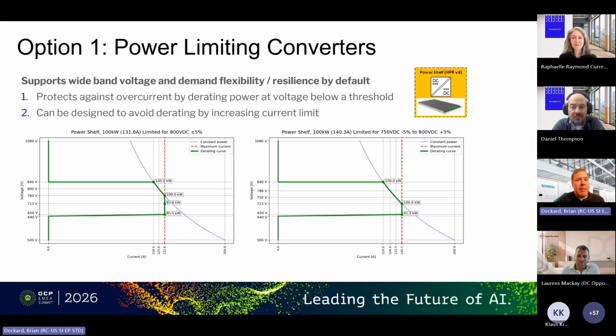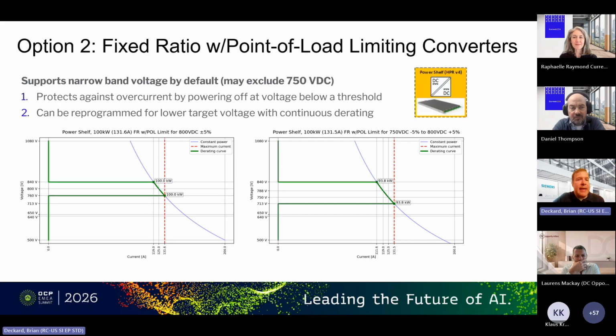Microgrids have traditionally embraced the power limiting capability you see with this red line, where you can follow a power curve as voltage drops, and then as it drops further, reduce power. We recognize this is not the only technology in use with data centers. For data centers, what we see is a lot of fixed ratio with point of load limiting converters, and these converters are unable to continue dropping in voltage because it would cause overheating.